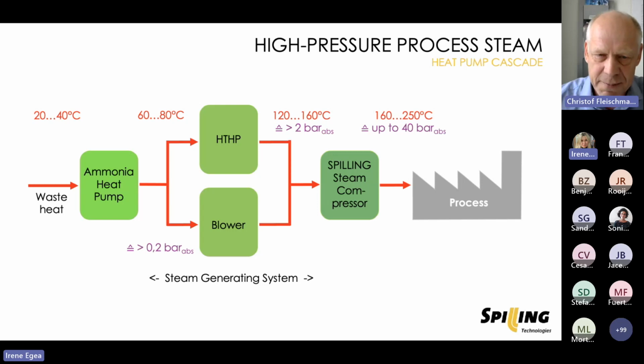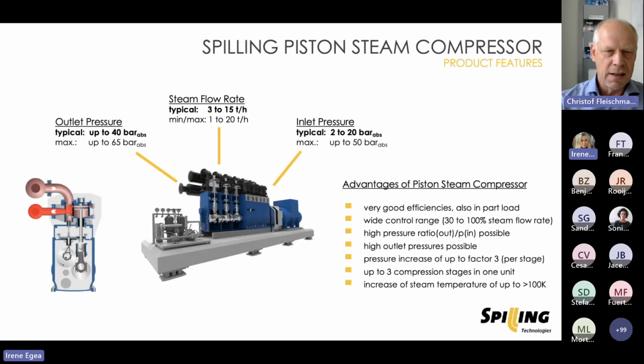Next slide, please. Now I would like to go a little more into the technology of these piston steam compressors. You see here a 6-cylinder unit. We built these machines with 1 to 6 cylinders. The number of cylinders is depending on the steam flow rate, which shall be realized with them, but also to the compression ratio, which shall be realized because we can combine these cylinders to up to 3 stages in one machine.